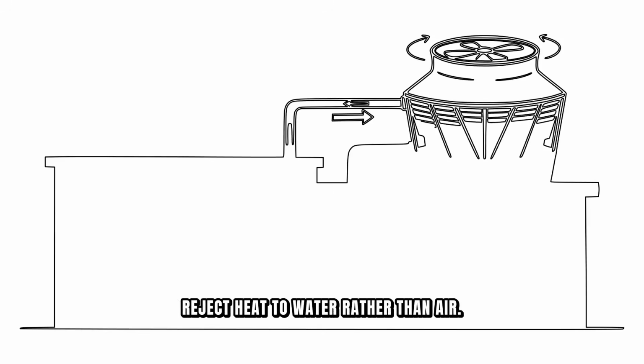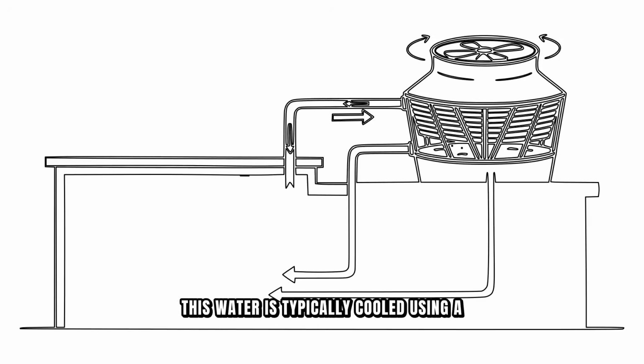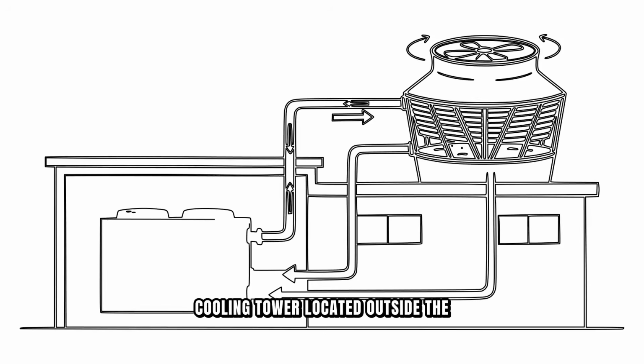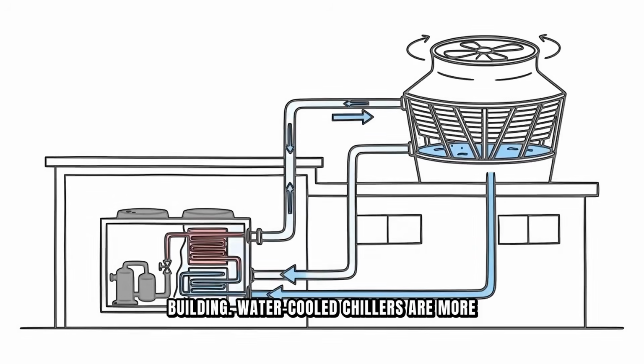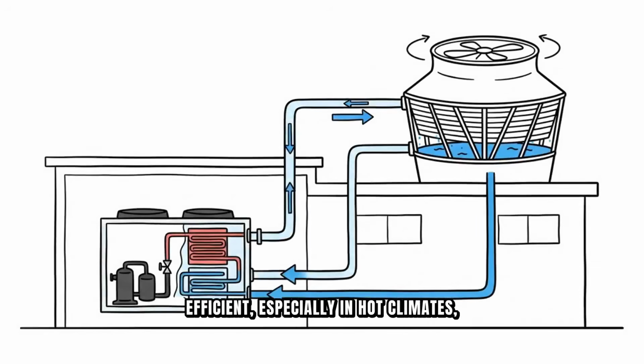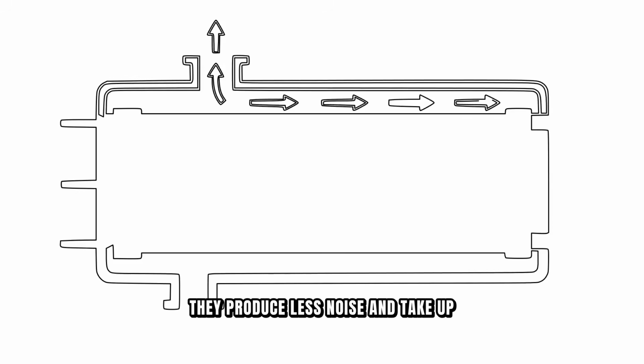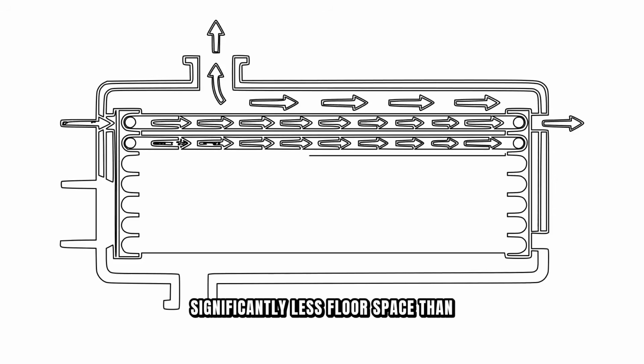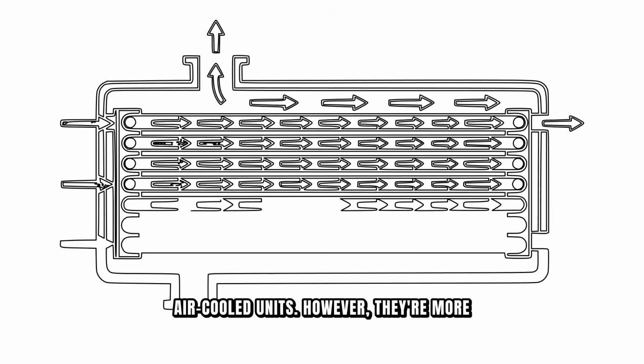Water-cooled chillers, on the other hand, reject heat to water rather than air. This water is typically cooled using a cooling tower located outside the building. Water-cooled chillers are more efficient, especially in hot climates, because water is a better heat transfer medium than air. They produce less noise and take up significantly less floor space than air-cooled units.